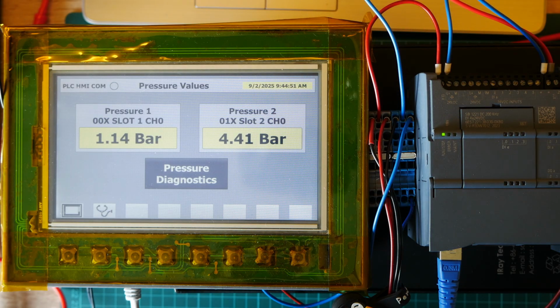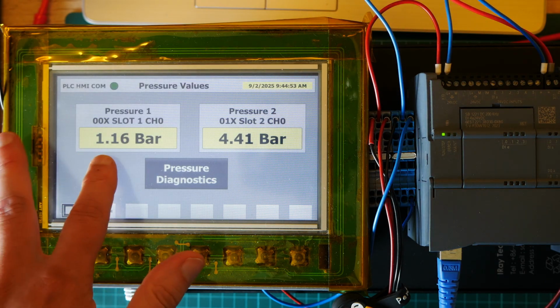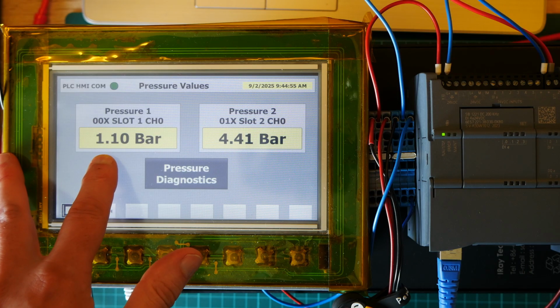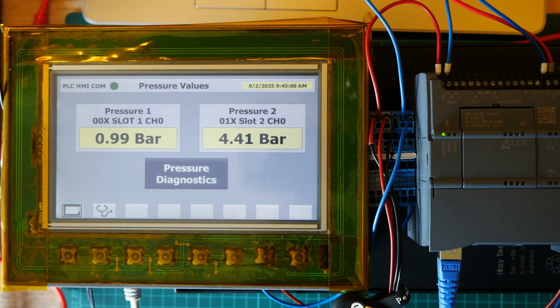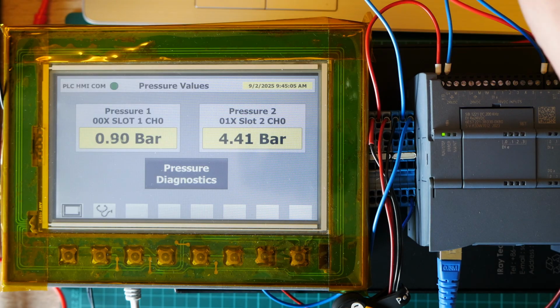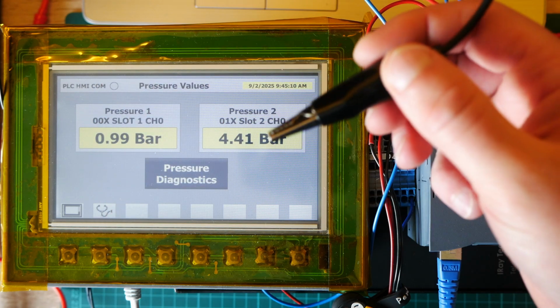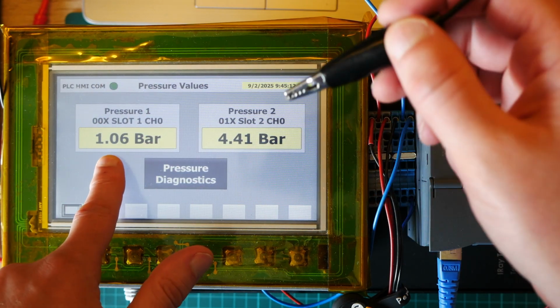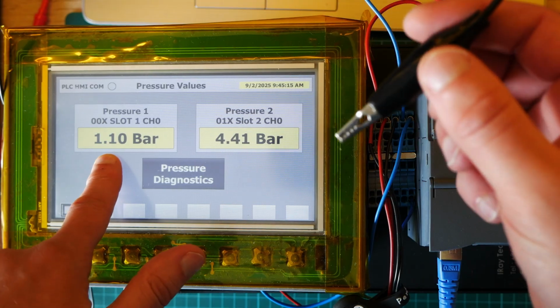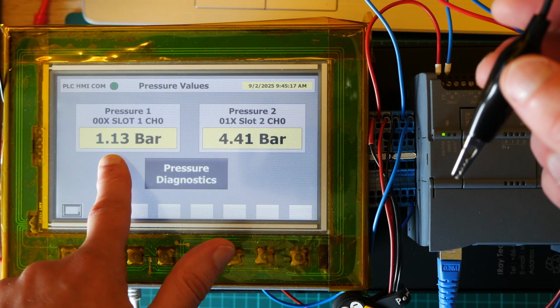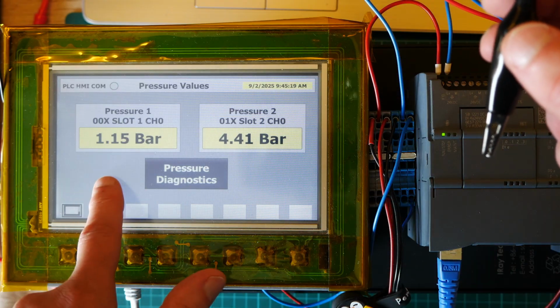Second case, let's say the wires are connected. Okay, there is no pressure, but it still shows a little pressure. Okay, it shows 1 bar. There is no pressure, it should show 0. The sensor is connected right now, so it could be an issue with wiring. Right now we have this 1 bar, but actually the negative contact is disconnected from the PLC.